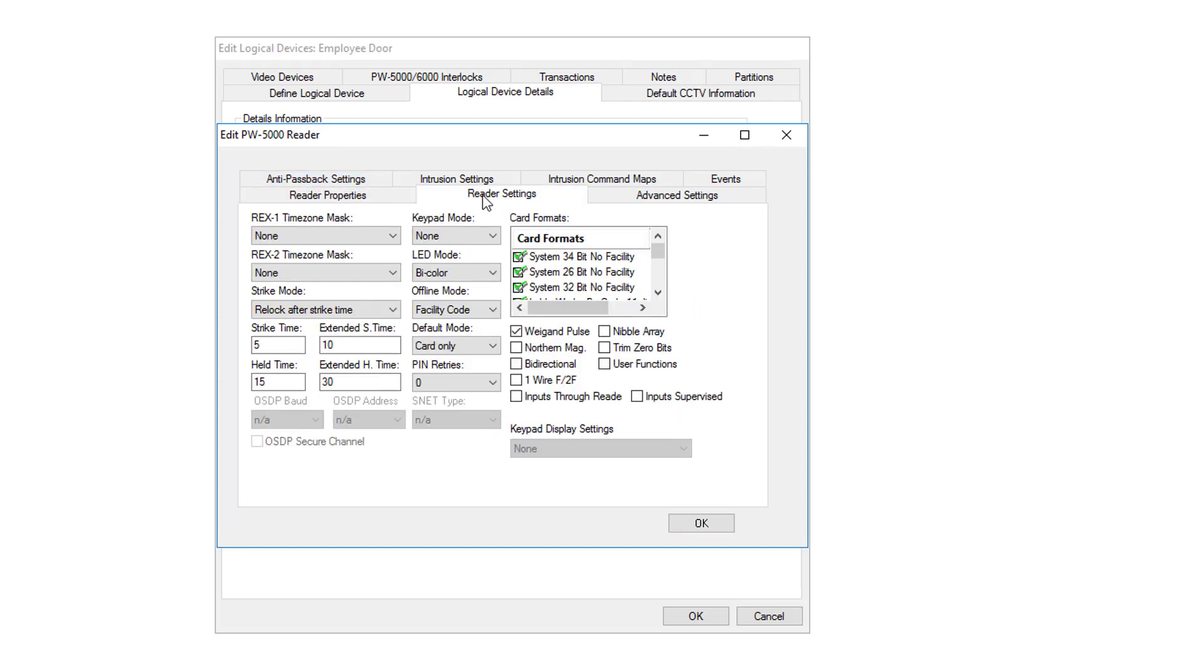This is where you can set up all your settings for your reader. In this case, we're going to look at the strike time and the held time. The strike time is how long the door will remain unlocked once it has a valid read. The held time is a countdown timer that once the door is opened and the timer has expired, before the door is closed, it will generate a held door alarm.